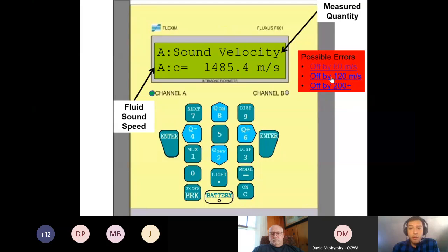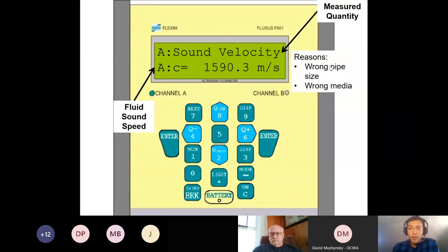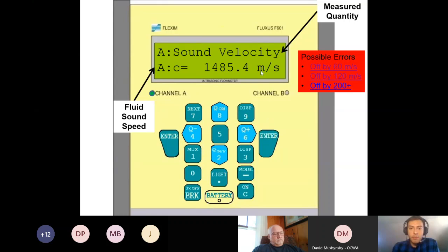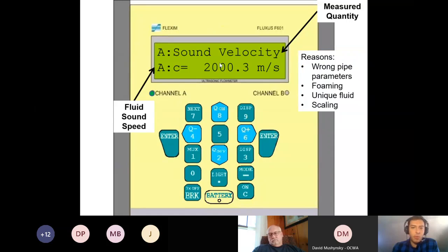If you're off by 120 or more, if you're off by a lot, this could be a wrong size pipe. Make sure you go back and measure the pipe again. Make sure you're getting the proper OD, that you're using the actual OD and not the nominal OD. Make sure you're choosing the correct media. Those are usually the key reasons why you would get a very off sound speed. That's if you're off by 120 or so, and then if you're way off, not even close, like I'm looking for 1480 and I'm at 2000, you definitely have the wrong pipe parameters. Go back through the parameters and make sure you're 100% sure about everything.